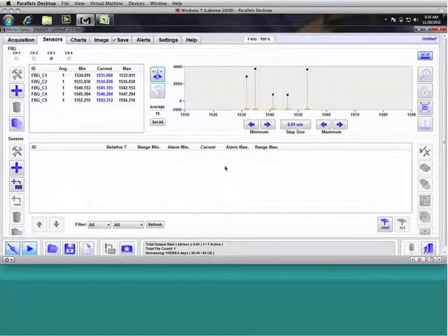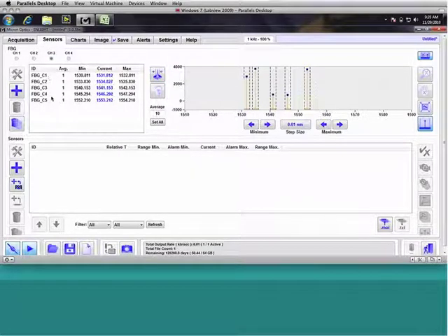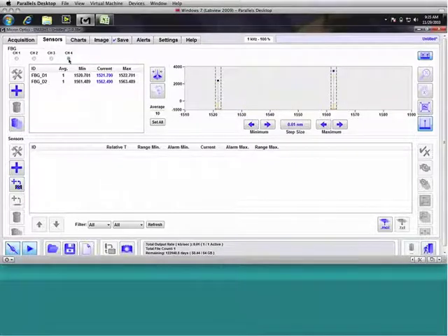Okay, and now we can see, and I'll go ahead and turn on the FBG limits for our display. We see that on channel 3 we have 5 FBG elements, which have been automatically named. Channel 3 is indicated by the C, so C for 3, D for 4, and then each of the FBGs is named in numerical order in which it was found in ascending wavelength order. Additionally, we can see that we have 2 FBG elements that were created on channel 4.